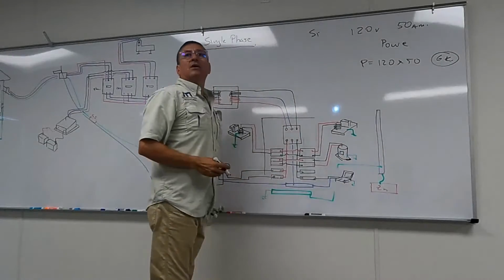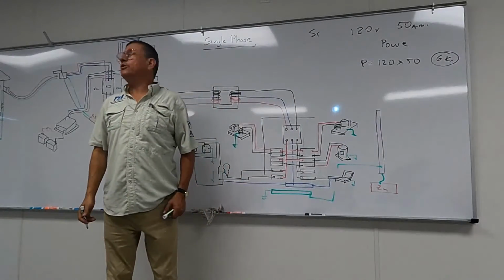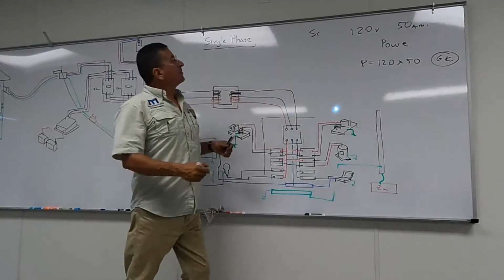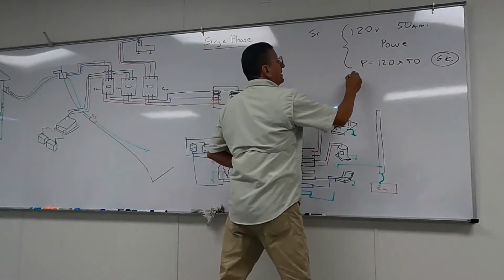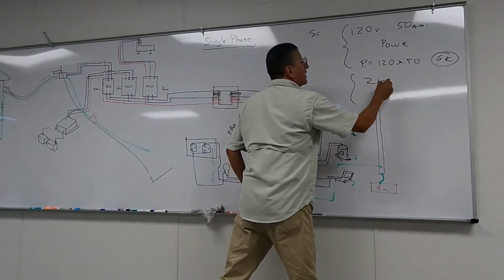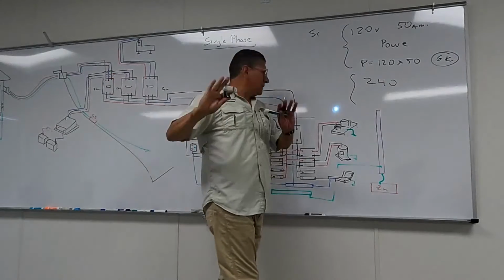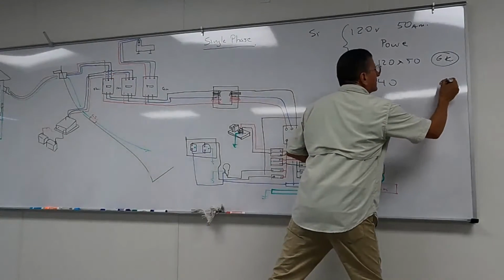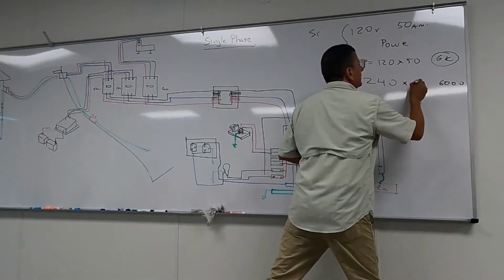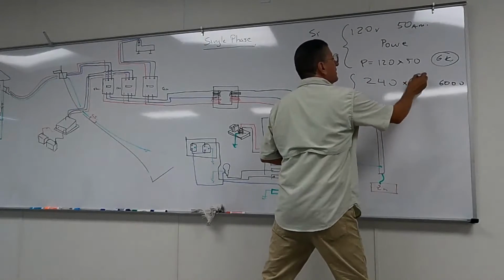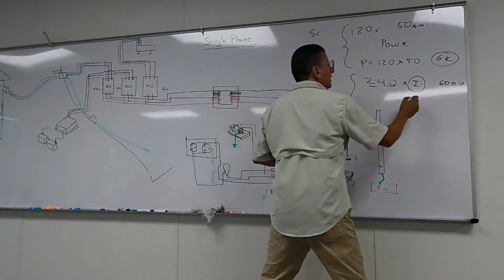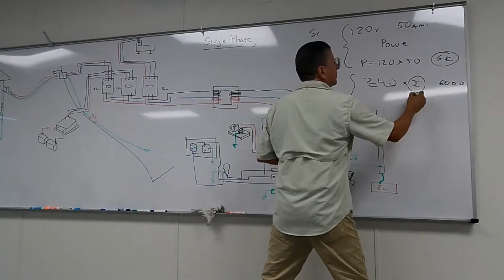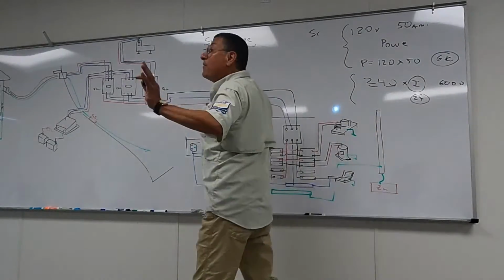Okay, 6 kilowatts. Now say I replace that air conditioner because it's too hot, with a new 240 volt unit. You still need 6 kilowatts of power, no problem, we'll get the same 6,000 watts. But now, what's the intensity needed at 240 volts? 25 amps. You need 25 amps. The power stays the same.